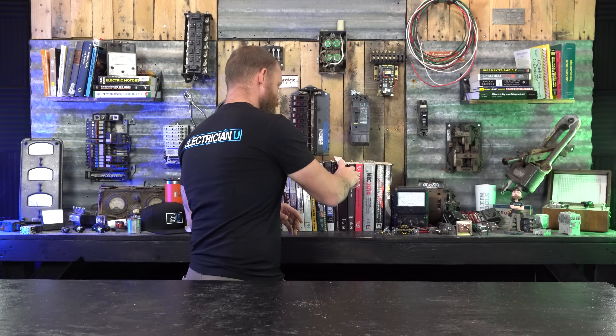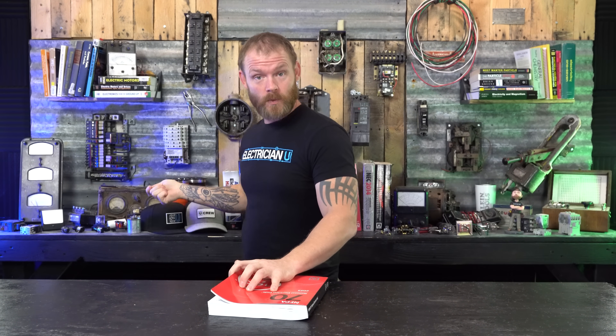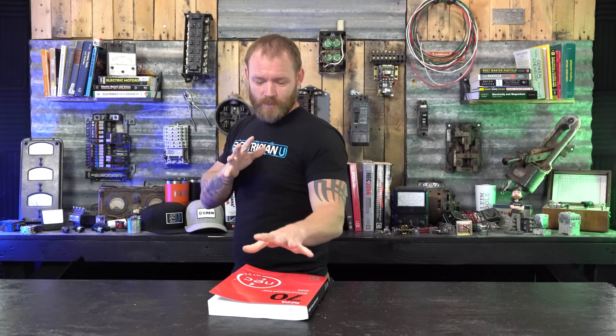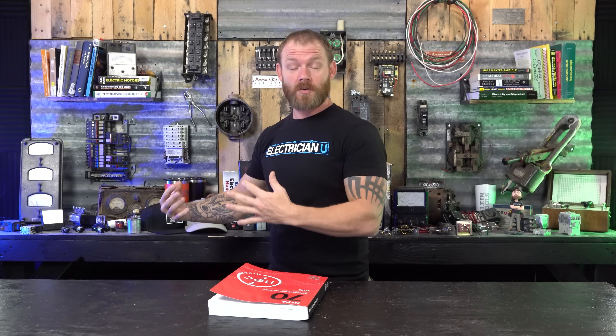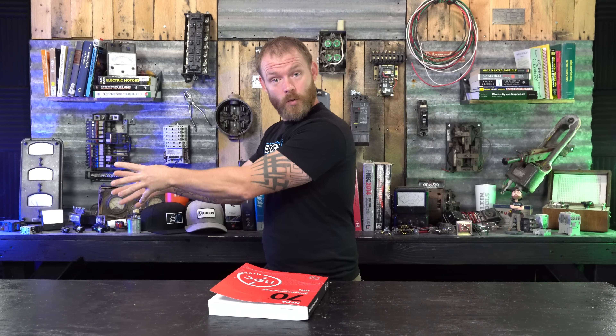Dual function is where there is GFCI protection and AFCI protection in the same breaker. So a dual function breaker is even more on steroids essentially because it'll protect if there's ground faults or both series and parallel arc faults. Now, what does code actually say about it? Where are we required to put AFCI devices in? This is really interesting because with GFCIs, we're specifically talking about receptacles where somebody could be standing in water — so it's to protect people, personnel. There's also places where equipment has to be protected too, like massive switchgear where a ground fault could send fireballs through a room.